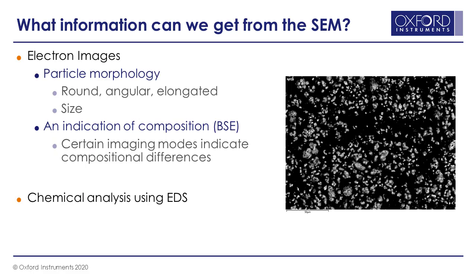We can create electron images using the SE or BSE detectors — secondary electron or backscatter electron detectors — giving us information about particle morphology: shape, size, and distribution. The backscatter detector is also sensitive to atomic contrast, so density variations. Based on the gray levels in the image, we can get indications about compositional differences. And if we use EDS — energy dispersive spectroscopy — we can analyze the X-rays coming off the sample and quantify those compositional differences that we see in the backscatter image.